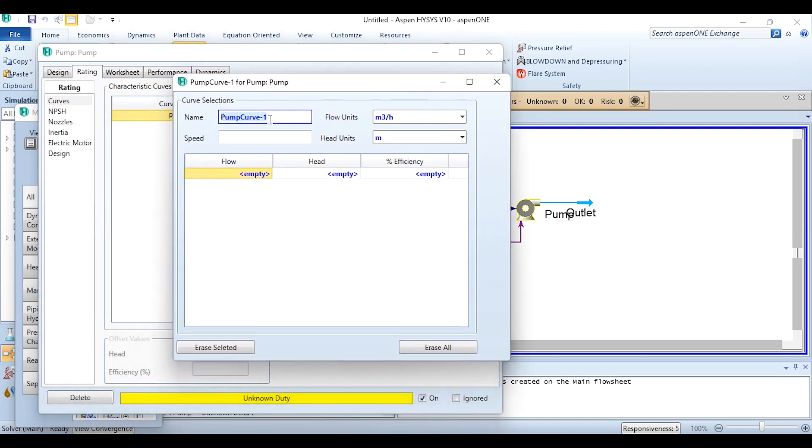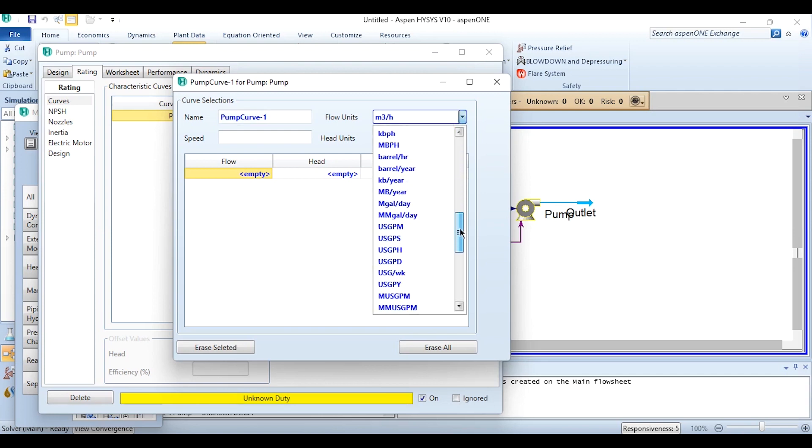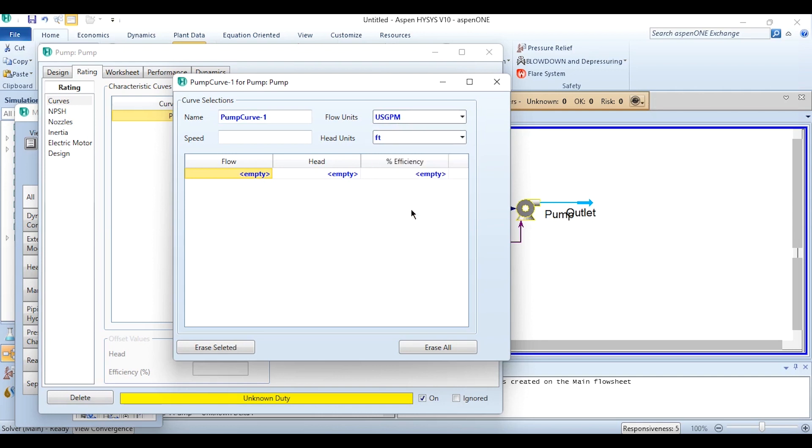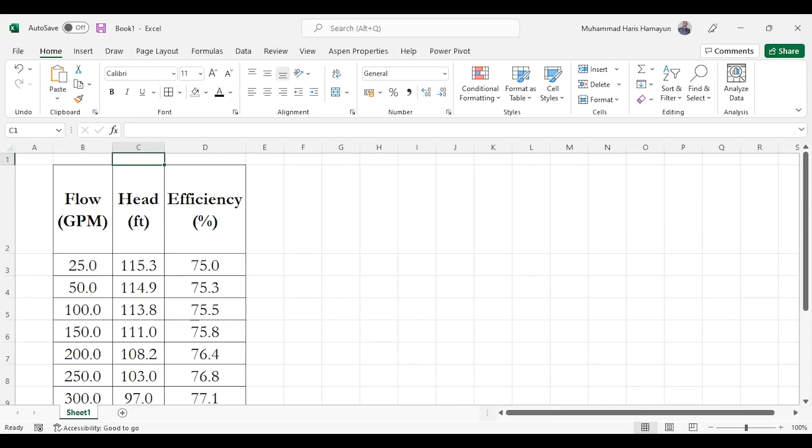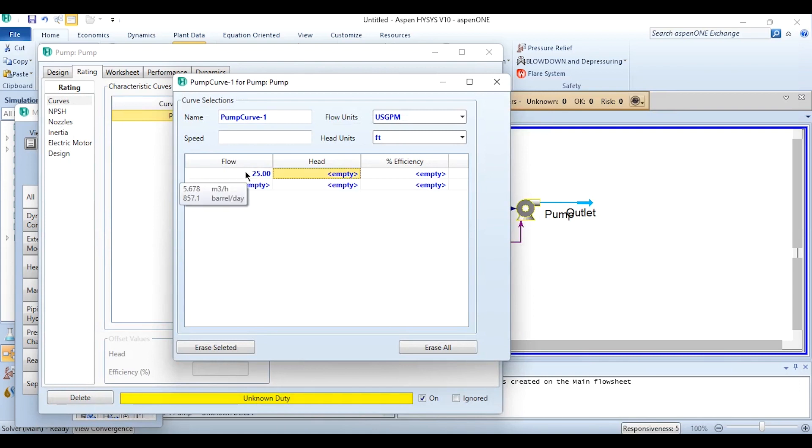Now this is Pump Curve, Curve One its name. Flow units we need to first change its unit to the required unit which is USGPM, and changing head units to feet. Now we need to specify flow, head, percentage efficiency. Speed can be specified as well if it is provided. In the current case we are not provided this value. So now what we can do, we can simply go back to the Excel sheet and specify one by one like 25 is the flow rate, 115.3 is the head, and 75 percent efficiency.